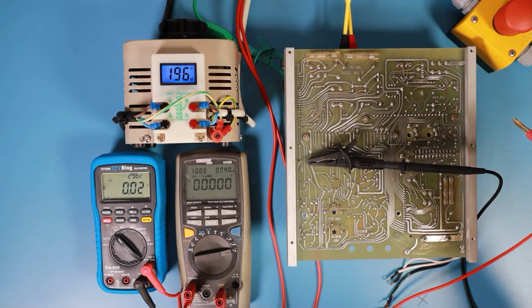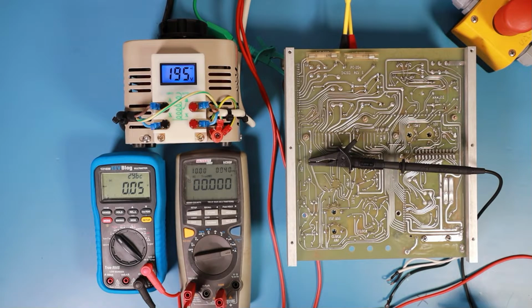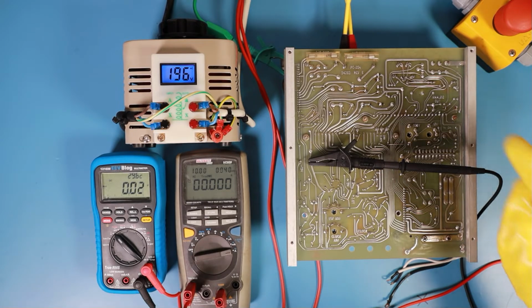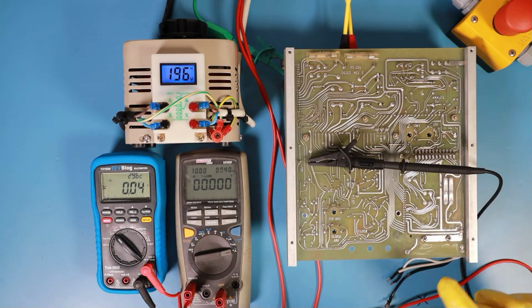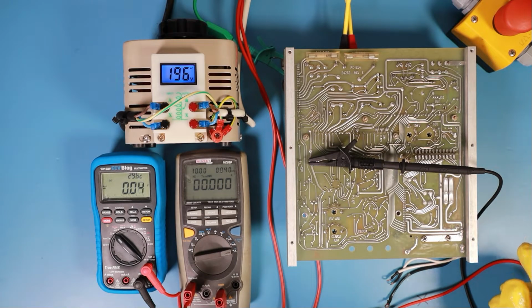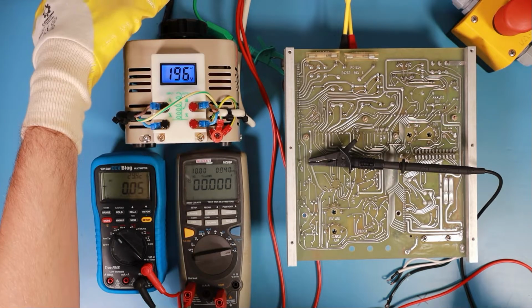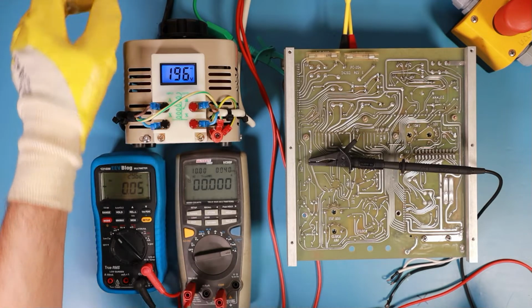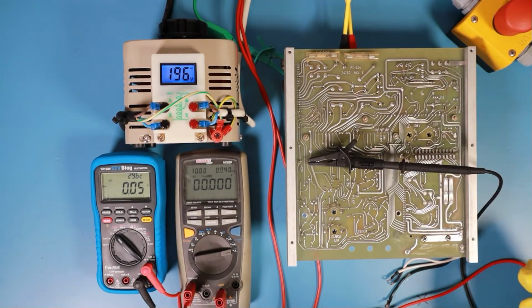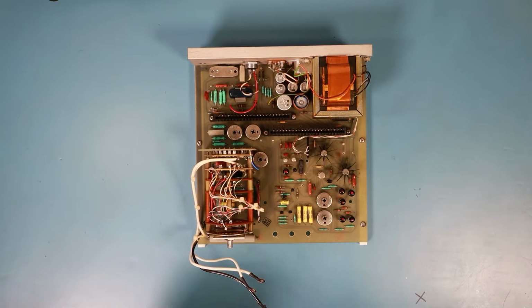So next step would be to install the modules again and then ramp up the voltage with the installed modules. And then we might see first if the device works and then if the 210 volt voltage range will be lower than it is at the moment. Because at the moment, when I turn the voltage up to get to line voltage, I think the voltage on this 210 volt voltage range would be too high.